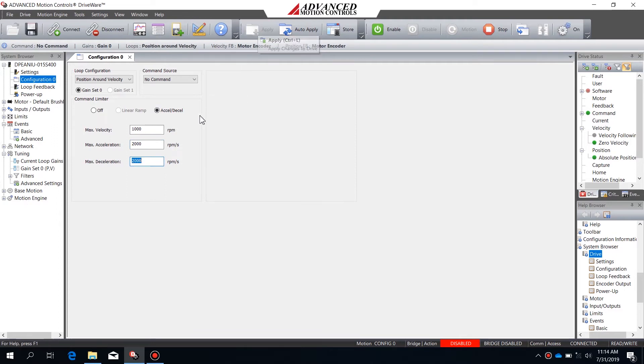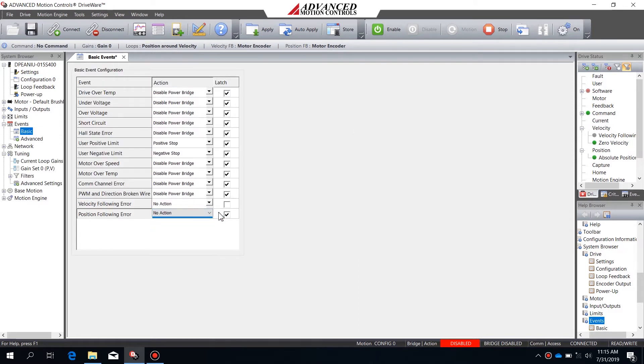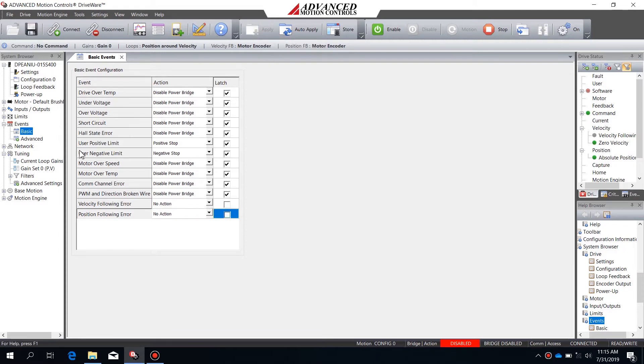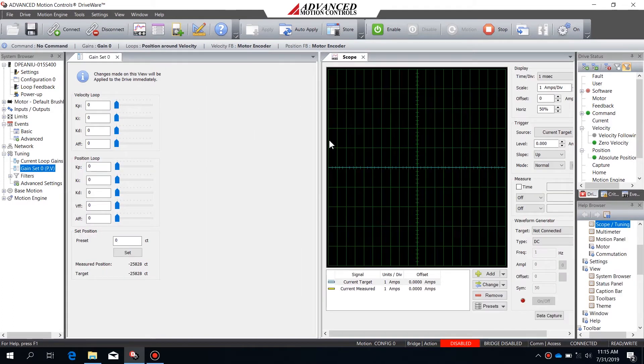I'm then going to go to my events and basic events and disable position following error. This will prevent the bridge from disabling while I'm doing velocity and position loop tuning. Next I'm going to open gain set zero and the oscilloscope so I can begin the actual process of tuning.